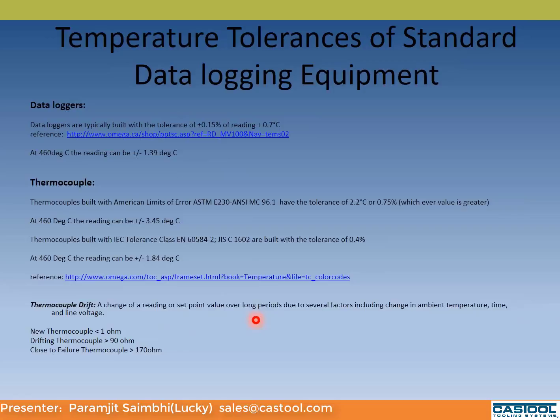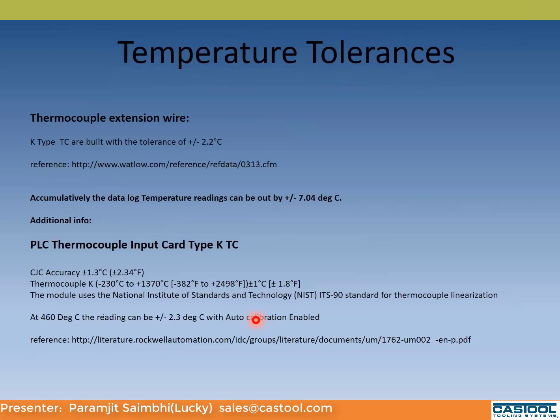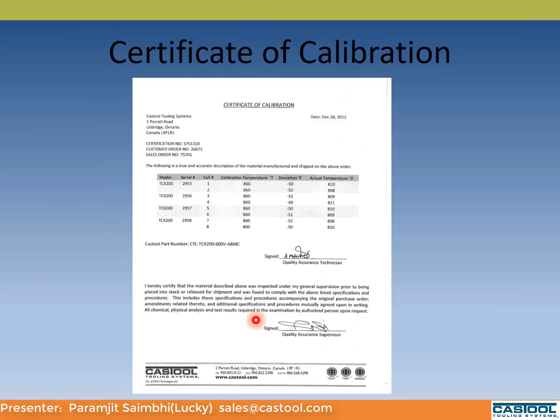And also the thermocouples, let's say you're putting thermocouples in a die and running tests. After a while, you would see drift on the thermocouples, so they do go out of tolerance. So you've got to keep that in mind. And we do provide a certificate of calibration if you hire Castool to come do the calibration on all the ovens.